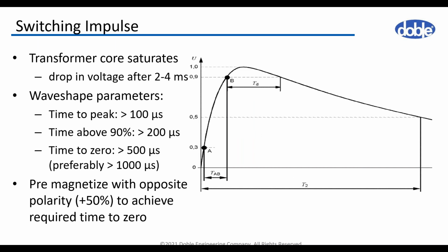The voltage is normally of negative polarity. During the switching impulse test, the parameters of the wave shape should be accomplished: time to peak of more than 100 microseconds, time above 90% higher than 200 microseconds, and time to zero more than 1,000 microseconds. A lower duration of the time to zero parameter is allowed in specific designs, especially for shunt reactors. It could be increased by inducing remnant flux in the core, by applying impulses of opposite polarity at reduced voltage between the test impulses at full test voltage.